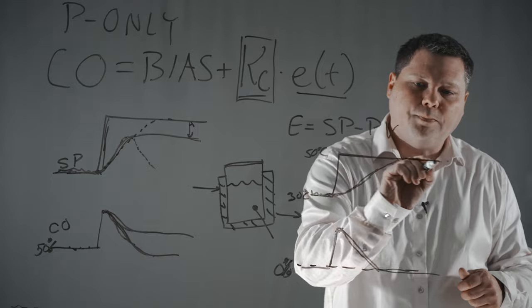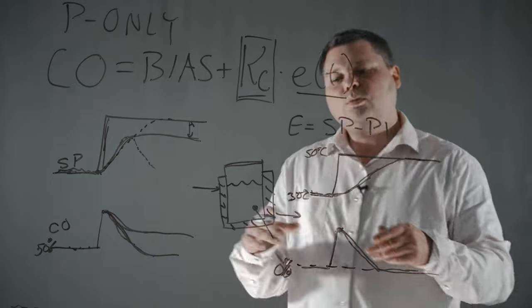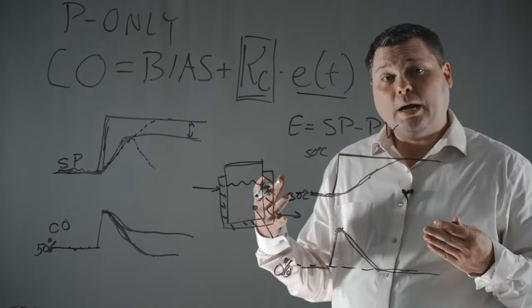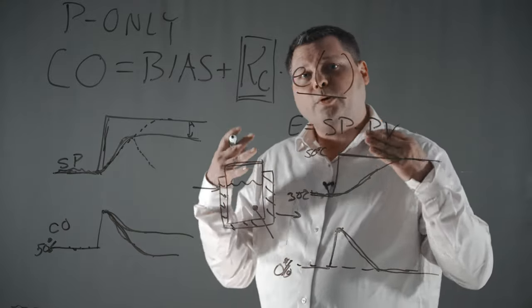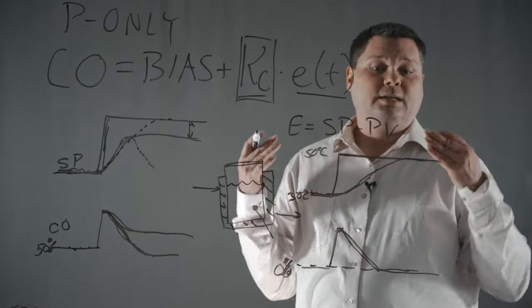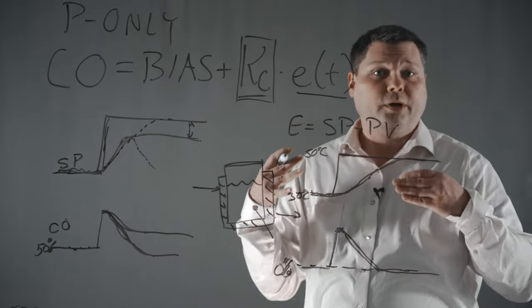So by moving it back to zero here, we actually have a balanced system. So this would be true for some batch temperature applications, some level control applications, systems where there's really only one steady type condition, one balancing point.